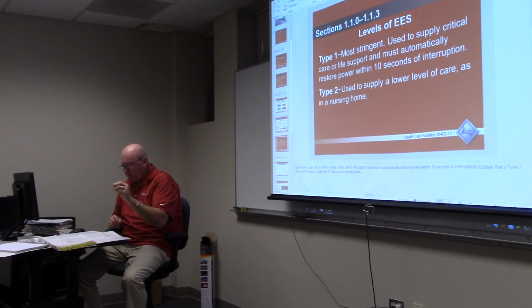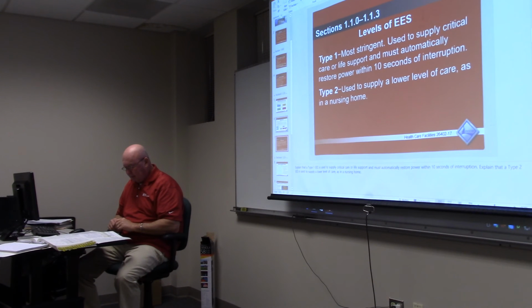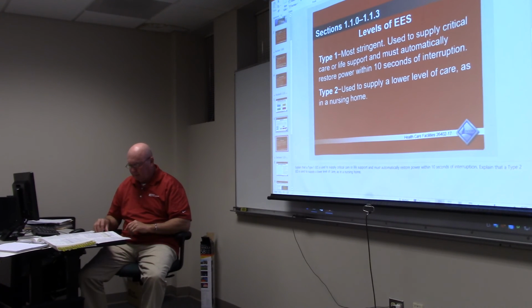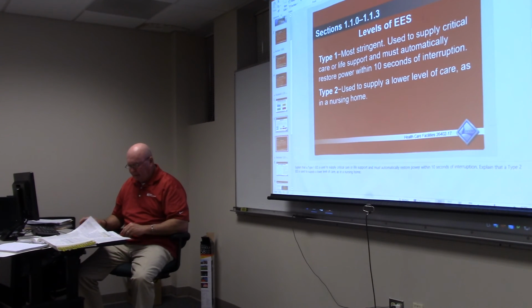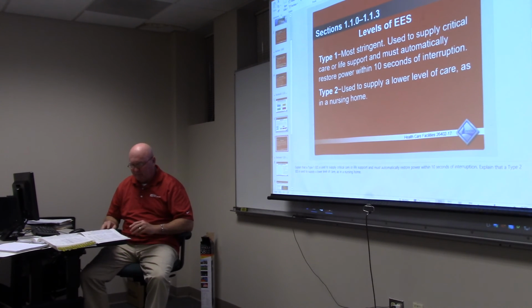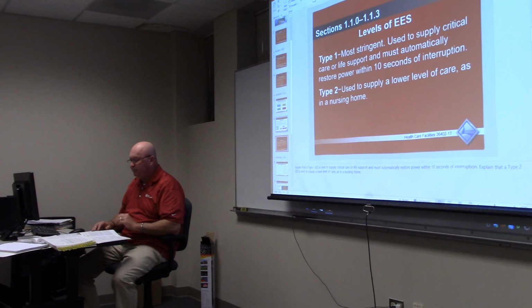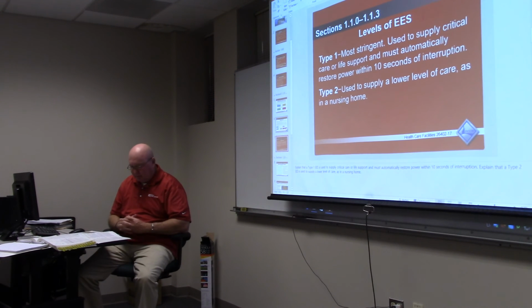In the third paragraph, the life safety branch must be installed and connected to the alternate source so there's not more than a 10-second delay. There are about 7 bullet points reflecting those areas in type 1. Our code blue button is on page 5, which we talked about earlier, a wall-mounted alarm device.